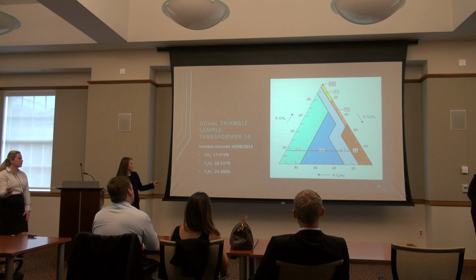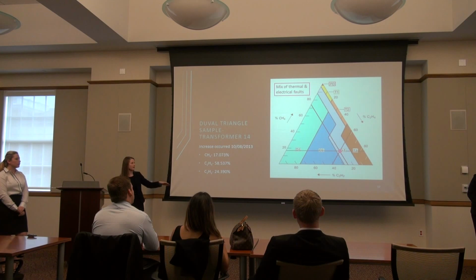Then for ethylene, the increase is about 58.5%, you can see that line on the ethylene side. And acetylene is about 24%, so you draw that third line, which pinpoints the problem in the DT range, meaning there's a mix of thermal and electrical faults.